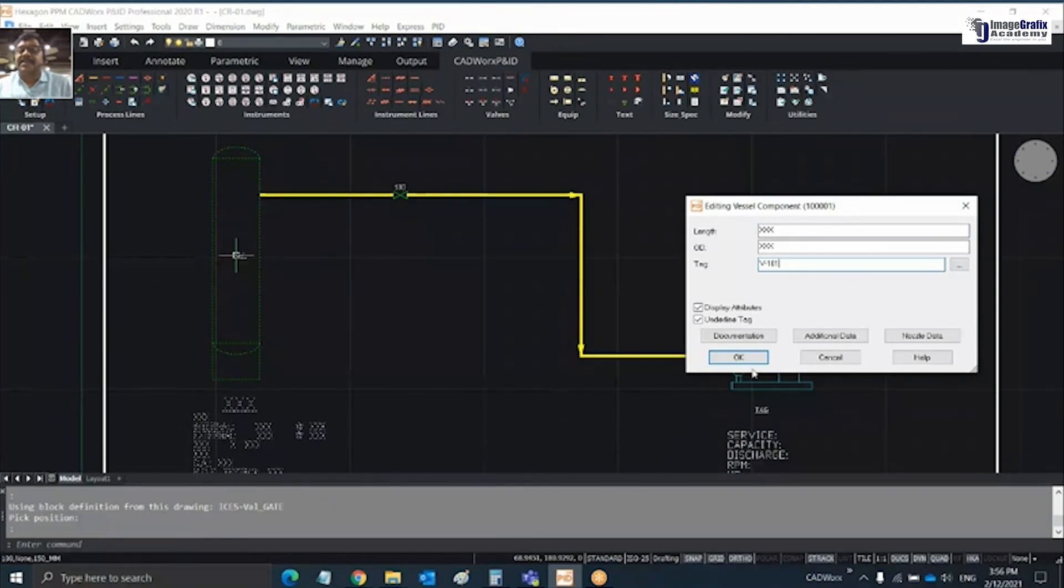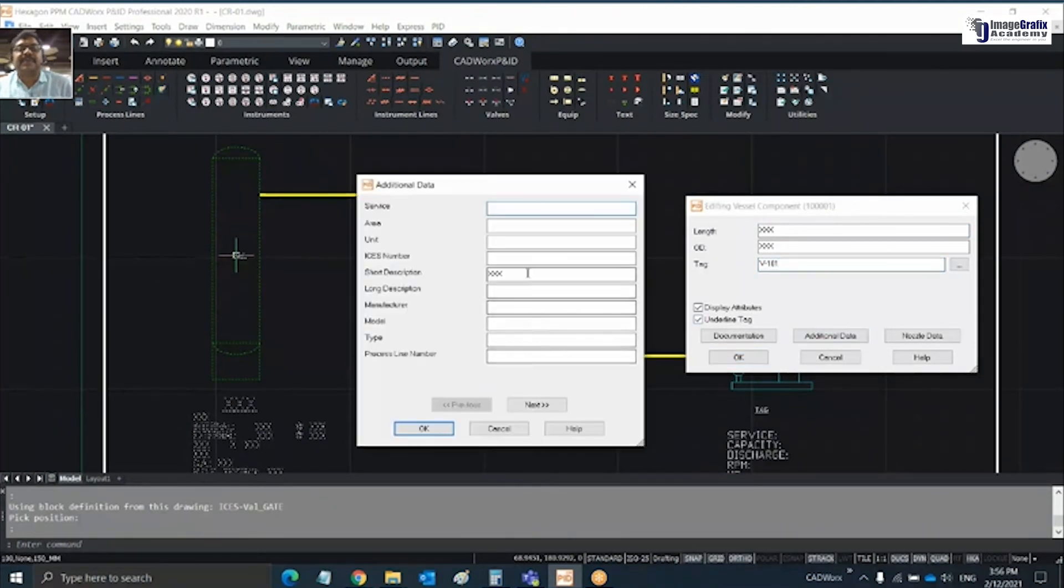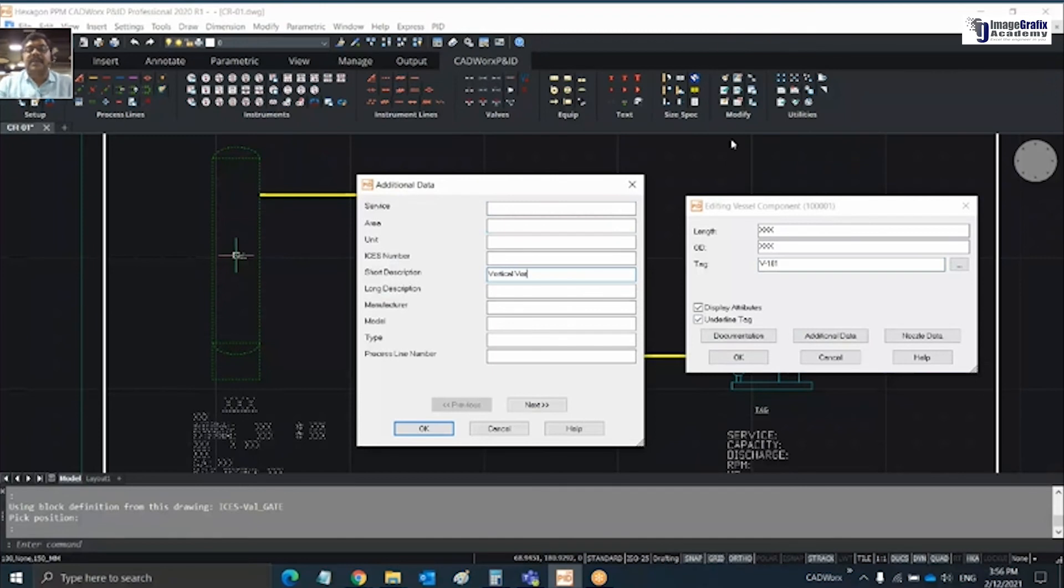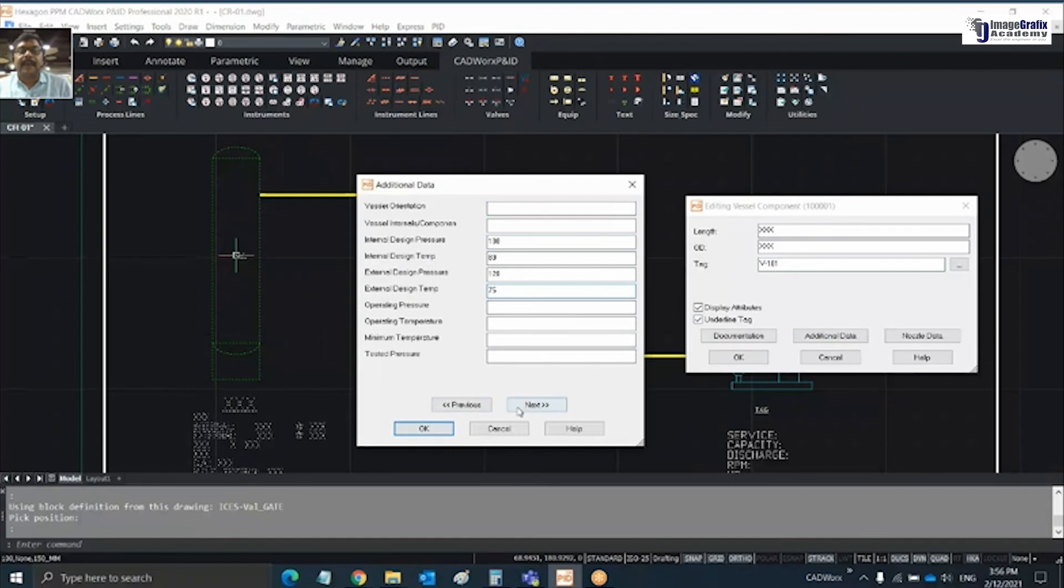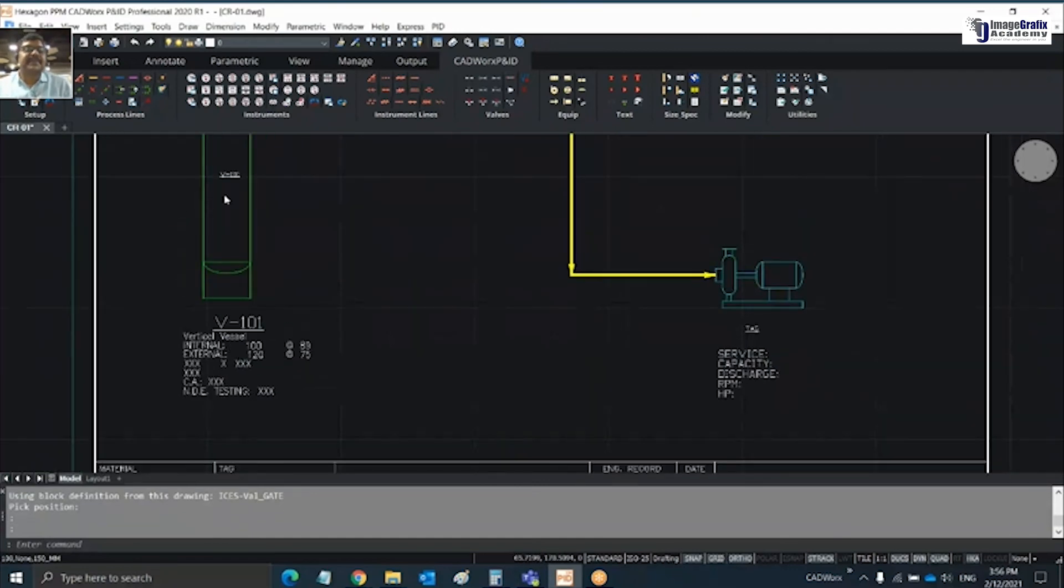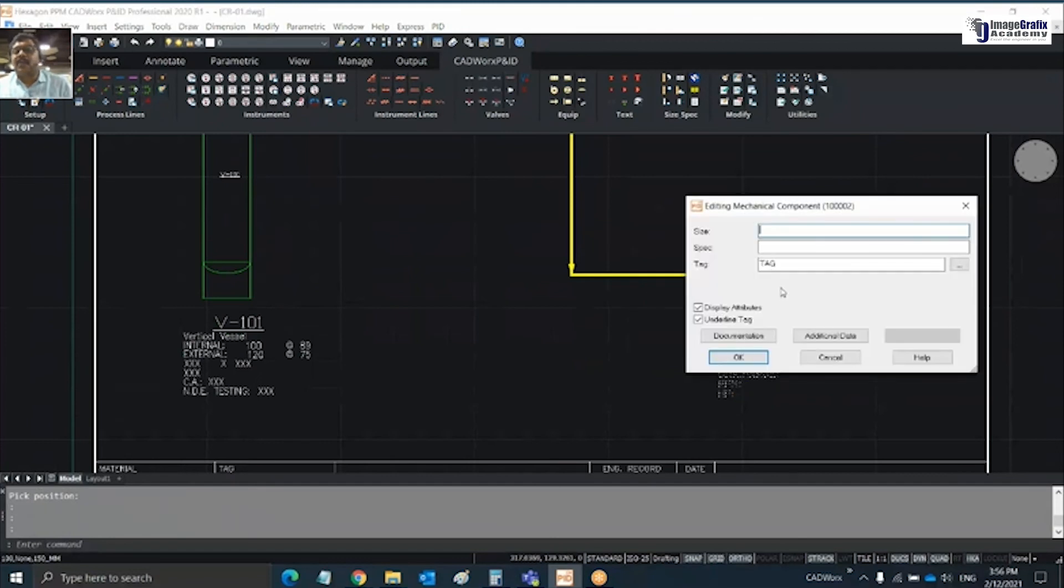Next I'm placing the tag for my vessel. This is going to be vertical vessel 101. Click OK. If you want additional information for the vessel like a short description, I'm naming this as vertical vessel. Internal pressure is going to be 100 bar, temperatures are 89, 125, 120, and 75 for example. Any other information you can add. Once you click OK, all this information for the vessel is updated.